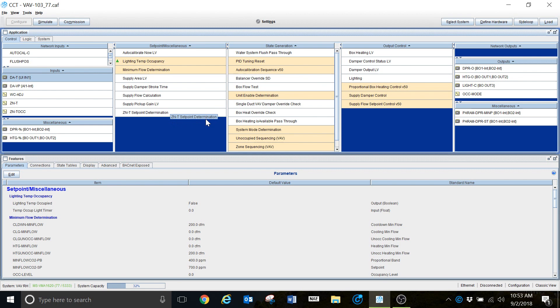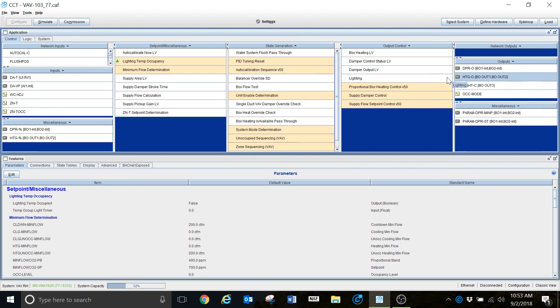One thing you will run into when troubleshooting a particular device is you're going to need to know what particular logic blocks control an output or control what you're trying to do. A way to discover that is quite simple. We're going to look at this heating output — this point right here. I want to know exactly what is controlling the heating valve on this VAV. Now that I have it highlighted, I'm going to right-click and get this little window here.